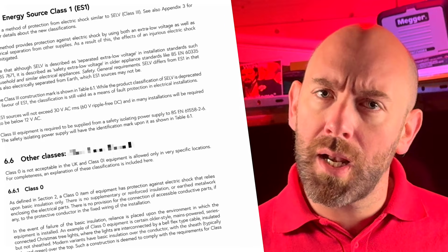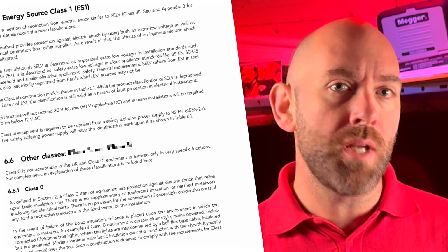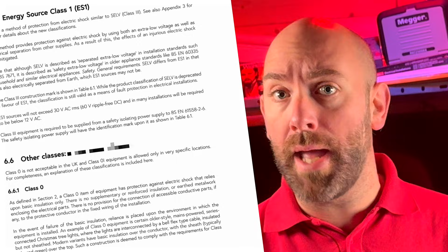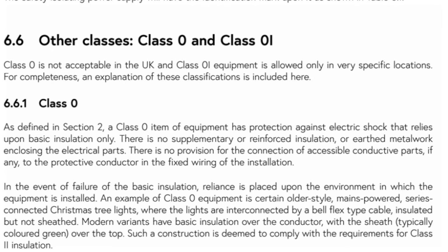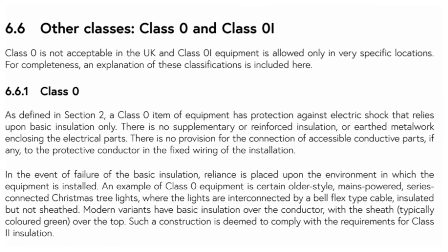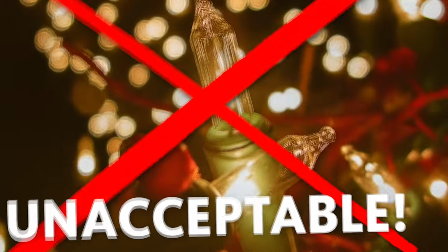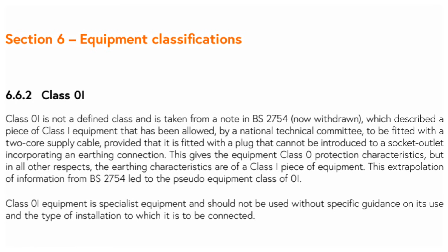We do have two more classifications featured in the Code of Practice, but they have no place in modern UK practice. Class 0 relies on basic insulation only. No supplementary insulation, no earth connection. If the insulation fails, the user is relying on the environment for protection, and this is unacceptable in the UK. Unacceptable. Class 01 came from a withdrawn standard. It describes equipment built as Class 1 but fitted with 2-core cable and a plug that cannot be inserted into an earthed socket. Neither Class 0 nor Class 01 should appear in normal UK workplaces.